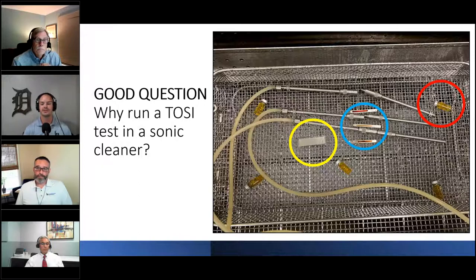So in this particular case, the ultrasonic lumen flushing slash cleaning function of the ultrasonic was not working. And I can tell you, because we ran this test and looked into what was causing the problem, we found out that the tubing supplying all the flow to those lumens was being kinked when the lid came down on the ultrasonic as we started the cycle.